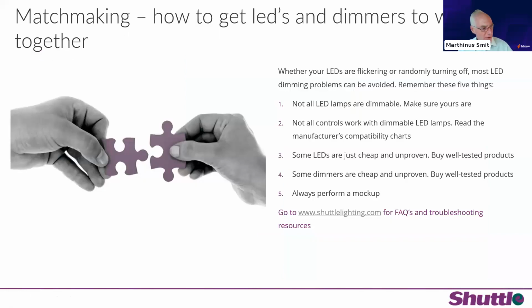So just to summarize, and I think my timing is absolutely perfect. There are many problems that we encounter with dimming LEDs. The problems are not going away. The problems are, in our opinion, actually increasing as the variants available in the market are increasing. The key is to make sure that, firstly, when your LEDs are fully dimmable, you use the same models on the dimming circuit. Remember that not all controls work on all dimmable LED lamps, so make sure of what the manufacturer specification says.